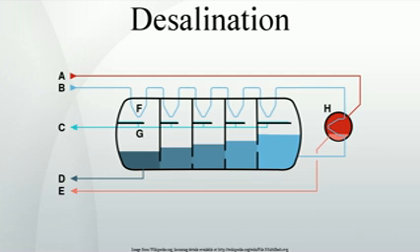Outflow. All desalination processes produce large quantities of a concentrate, which may be increased in temperature, and contain residues of pre-treatment and cleaning chemicals, their reaction byproducts, and heavy metals due to corrosion. Chemical pretreatment and cleaning are a necessity in most desalination plants, which typically includes the treatment against biofouling, scaling, foaming and corrosion in thermal plants, and against biofouling, suspended solids and scale deposits in membrane plants.